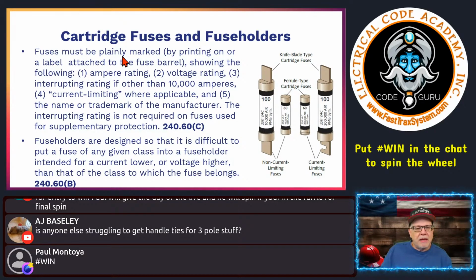So fuses must be plainly marked and printed on a label attached to the fuse barrel, as you see here, showing the following. It has to have the amp rating, the voltage rating, and the interruptive rating if it's other than 10,000. So you remember the 5,000 for the circuit breaker, unless marked otherwise, and 10,000 for the fuses, unless marked otherwise. For current limiting, where applicable: if you have current limiting fuses, they have to be marked as such. And the name or manufacturer trademark on the actual product.